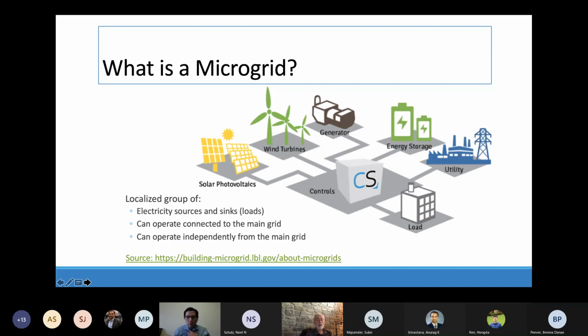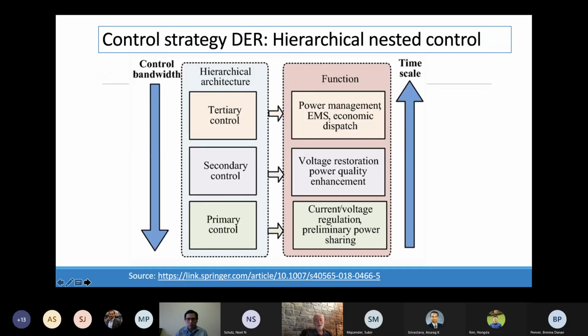So a microgrid is, formally speaking, a localized group of electricity sources and sinks that can be either connected to the main grid or operating independently from the main grid. As we see here, it has renewable resources such as wind turbines and solar that can be scaled from a few kilowatts to a few gigawatts. And then it may contain other traditional generator sources like rotating machines driven by gas turbines or diesel generators. It can contain energy storage, and it may still be connected to the utility and have load. So all of those things could, but do not necessarily have to, be part of a microgrid.